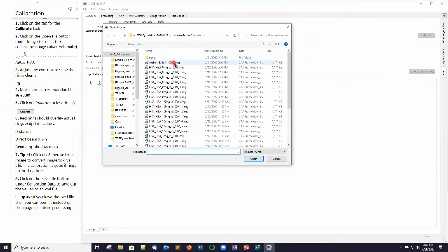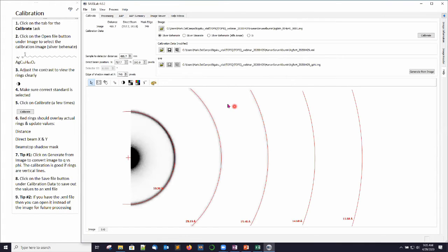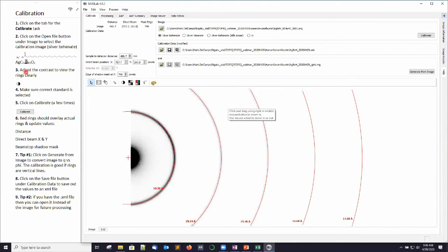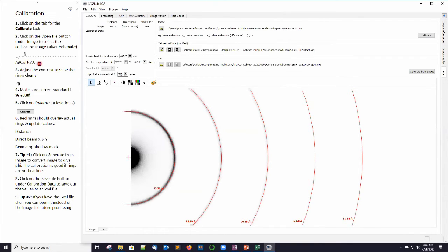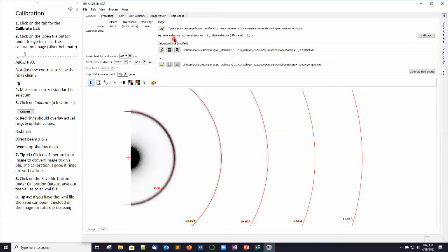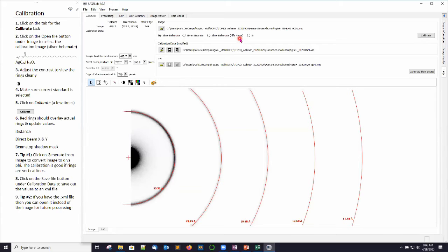The next order of business is calibration. We're going to make sure that we click on the top left on the calibrate task. And then we're going to click the open file button under image. And we're going to want to select our calibration image. So I'm using a Silver Behenate standard image here. I select it. I click on open and the image opens in the software. In case you're interested, this is what Silver Behenate looks like on the left and its chemical formula. Silver Behenate is a commonly used standard for calibrating SAXS instruments. You'll notice at the top of the screen which calibration powder I'm using is important to be selected. So I have the first radio button for Silver Behenate selected. And I will tell you this, this is from Kodak.